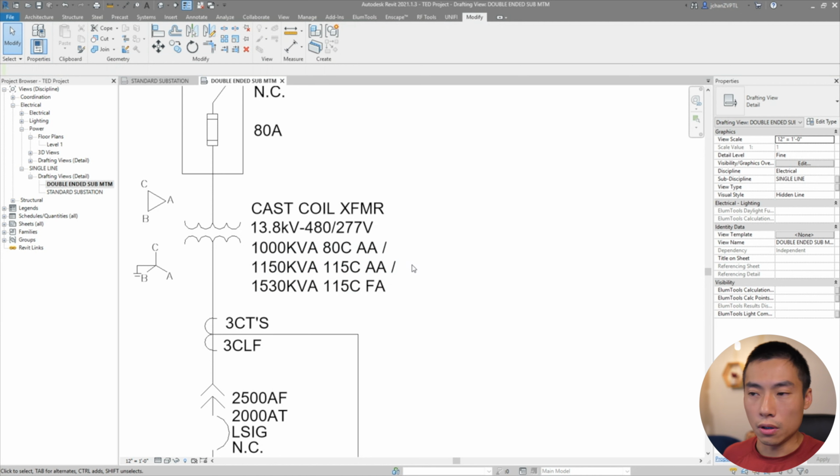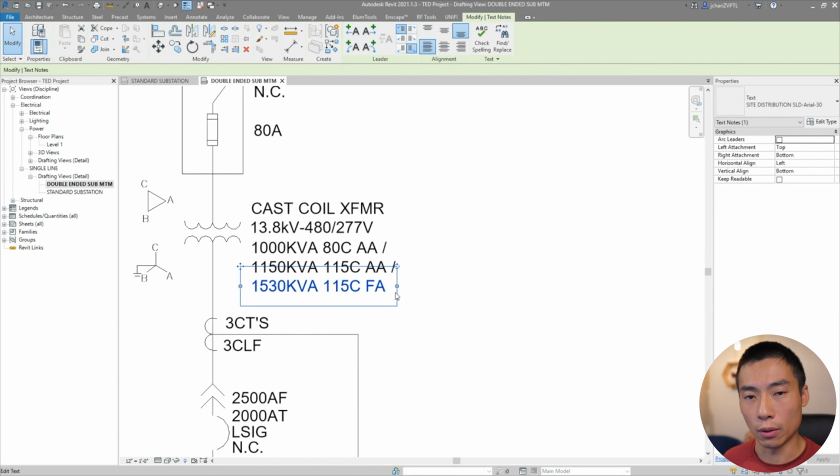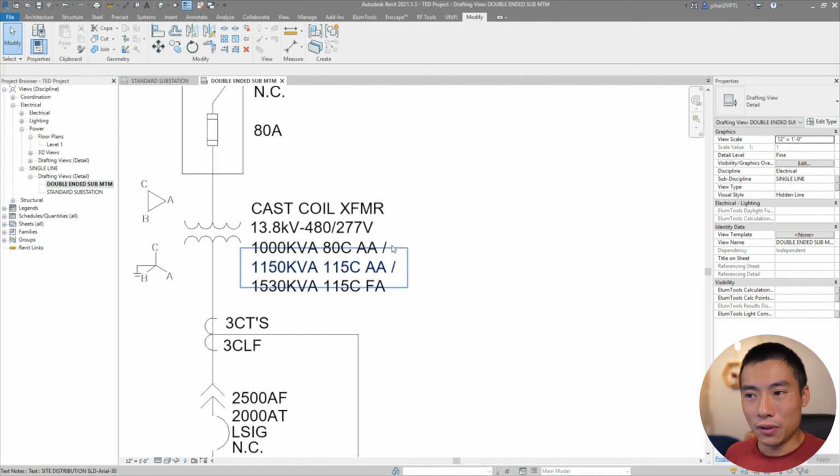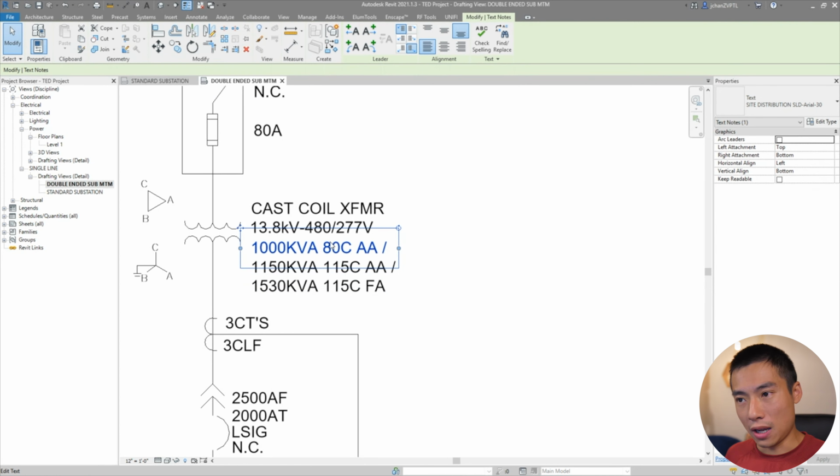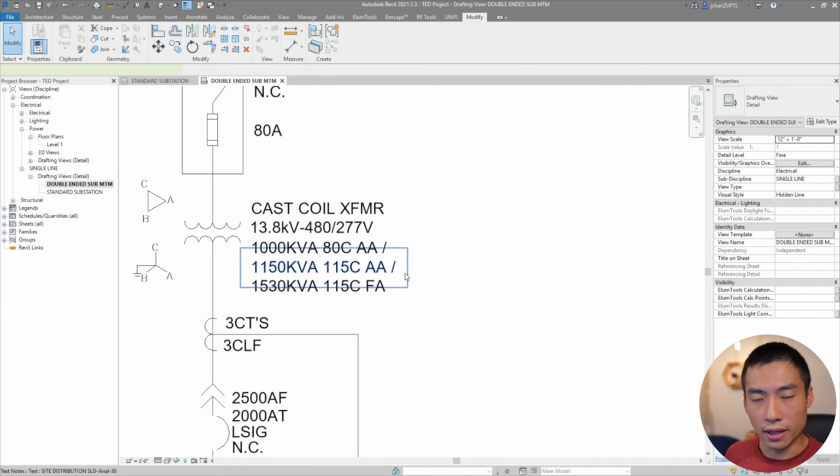Then it's more reliable because you don't have to rely on your last setting, which is a forced air using a fan. The fan may never run for years, and all of a sudden, if you need it and it doesn't kick on, you're not getting that rating. So I like to design to 50% of your 80C AA. Then if you need a single N, you shouldn't exceed 115C AA.